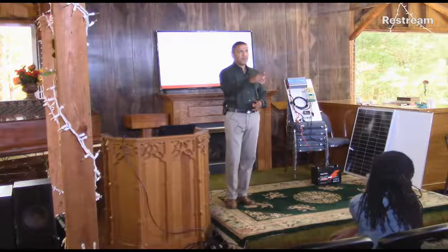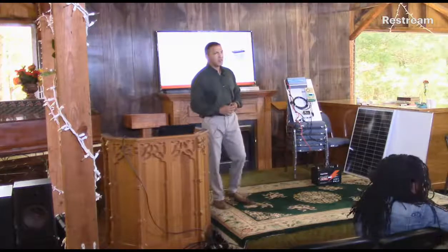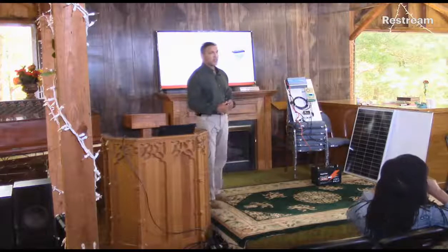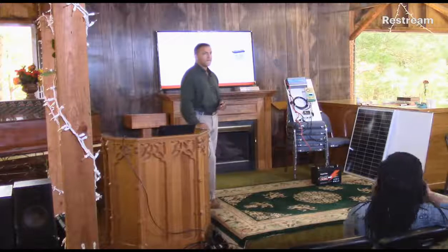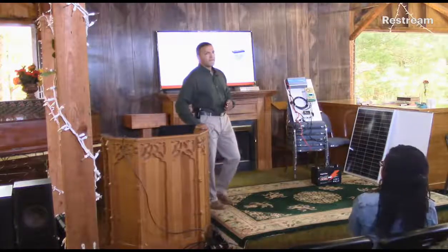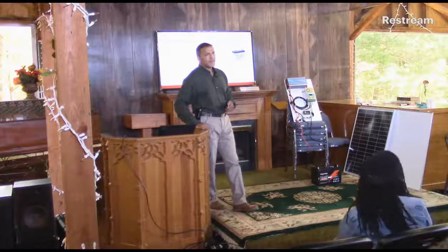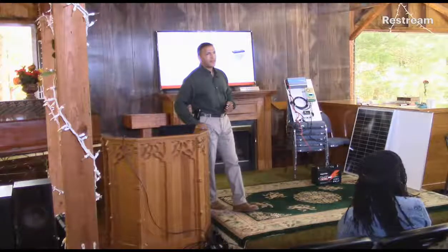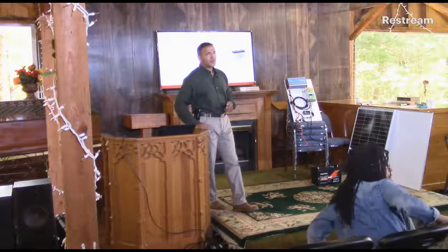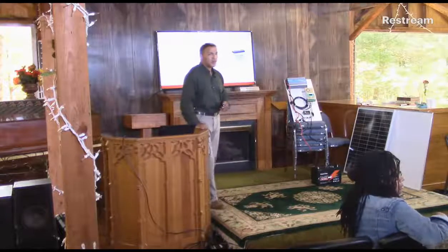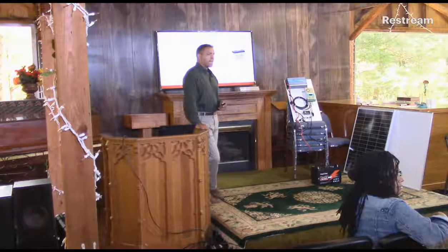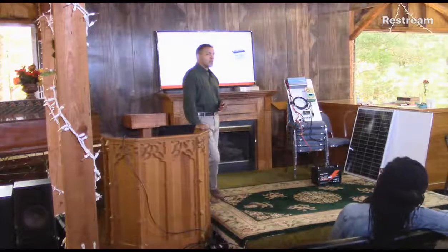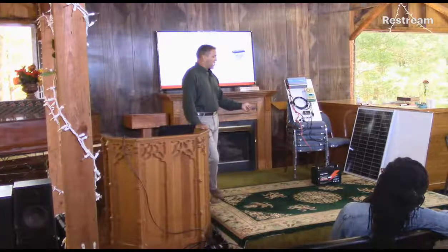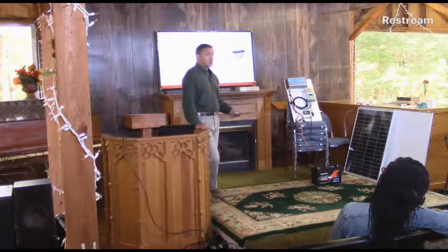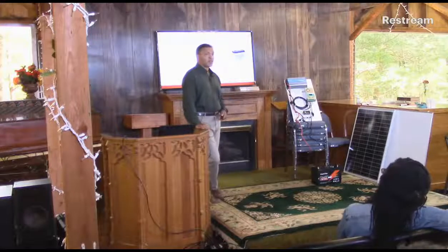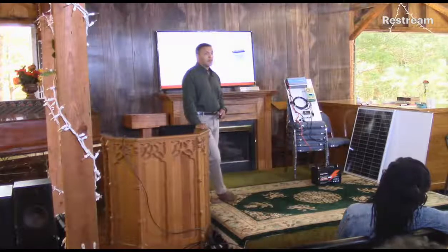On lead acid batteries, I've read that when discharging you don't want to exceed a certain rate. Say it's a 100 amp hour battery, you'd want that 100 amp hours to last over 2 hours, so you wouldn't want to put more than a 50 amp load on it. Is that also true with lithium batteries? No. Most of these batteries are rated for 100 amp discharge current, you could discharge at 100 amp and it doesn't bother it.